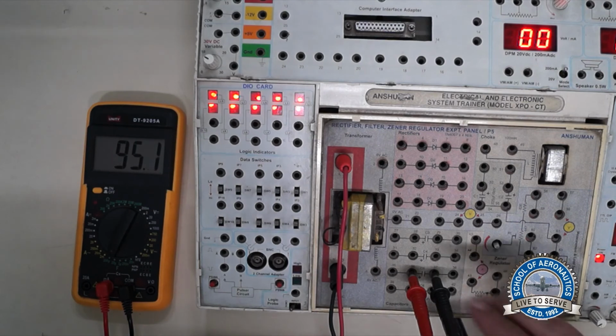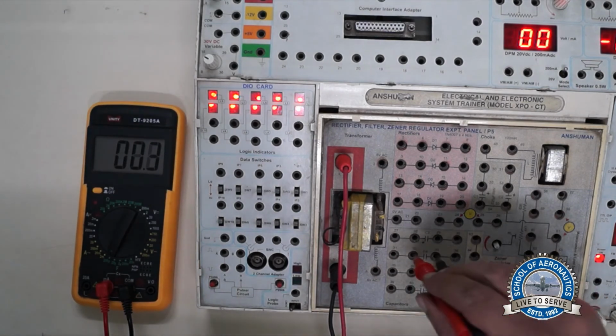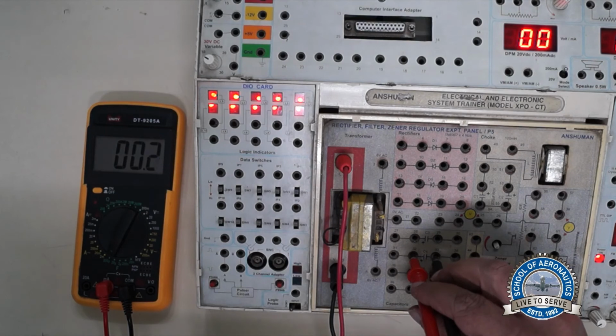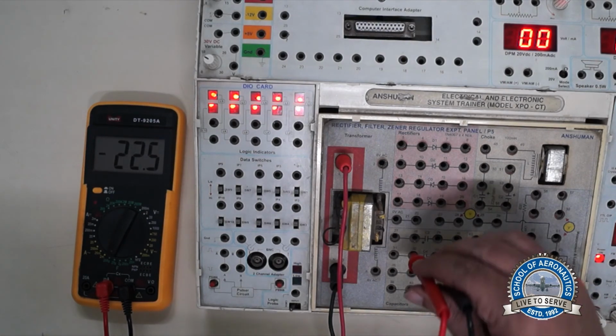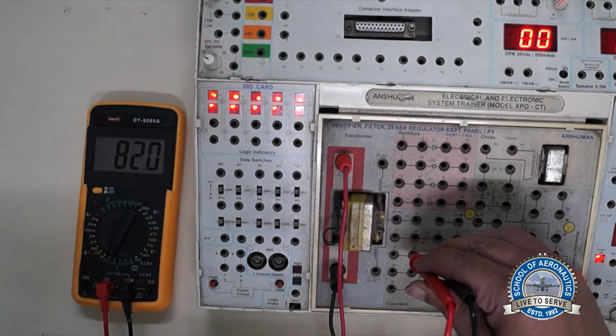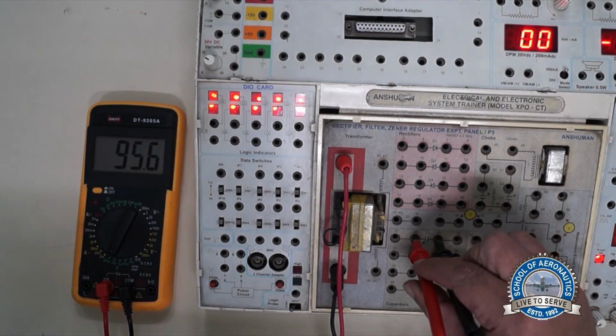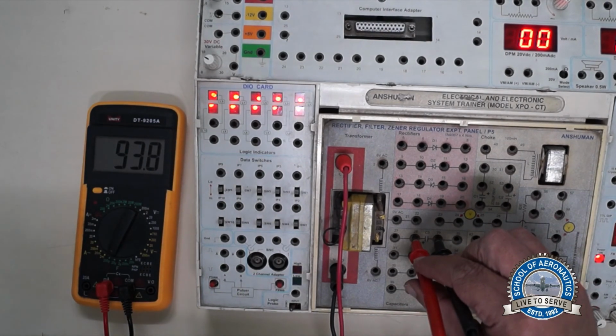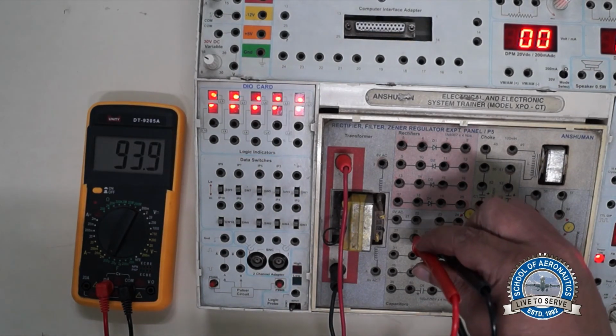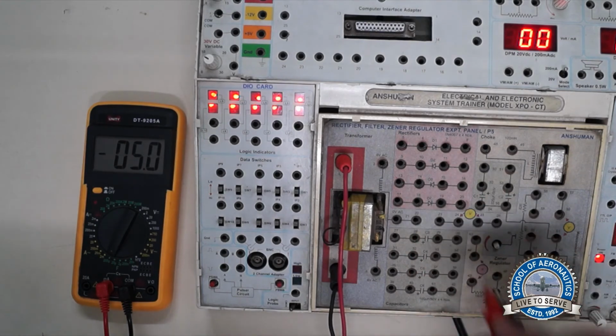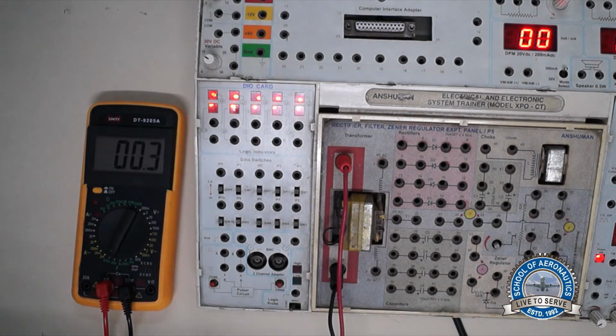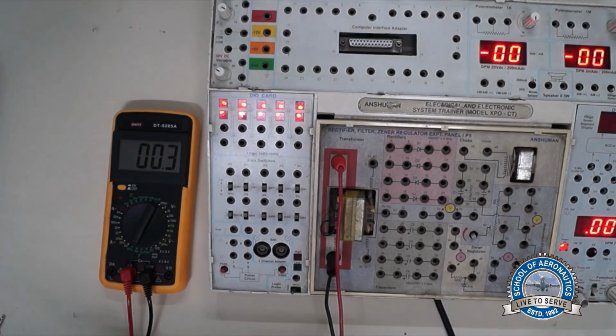So it is 95 showing. Same four capacitors are there. It's showing 82. It is saying 93. Maybe some tolerance is there. Anyway, all the four capacitors are working. You are measuring them at the same time. Also, you can say you are testing. The value is showing, which means that way also you can say it's testing. We are testing and it's working perfectly.